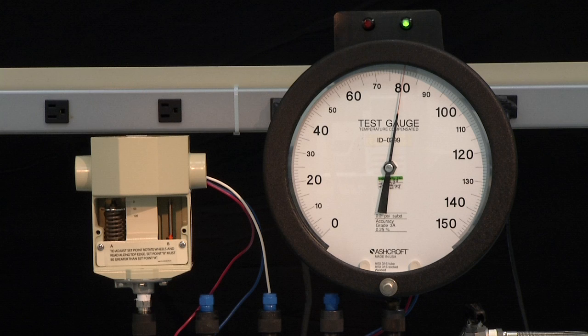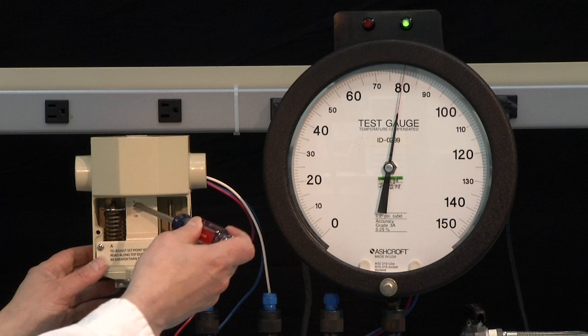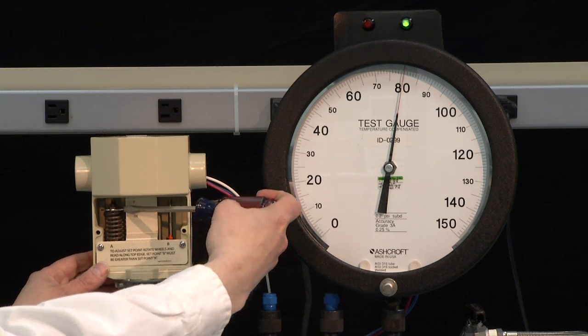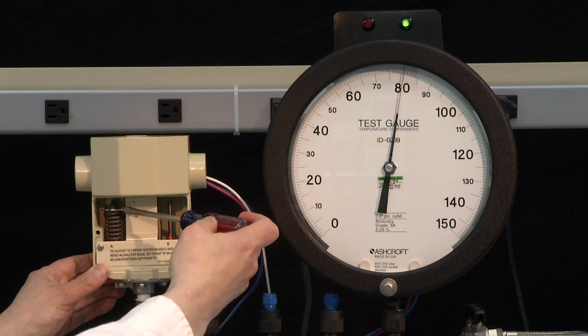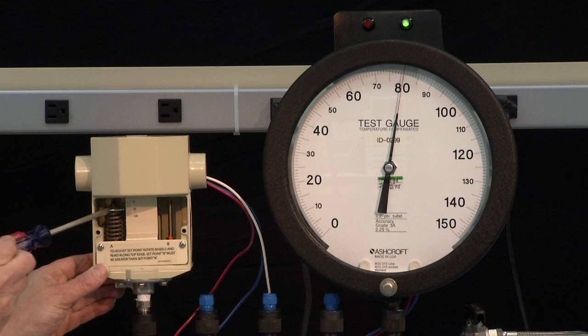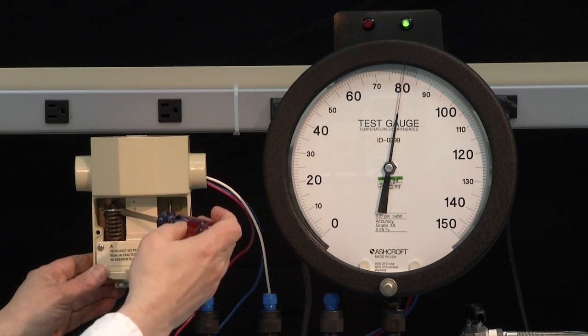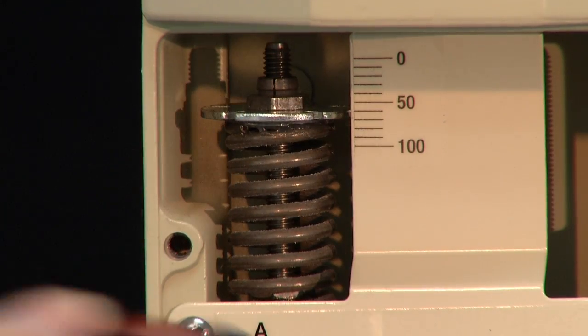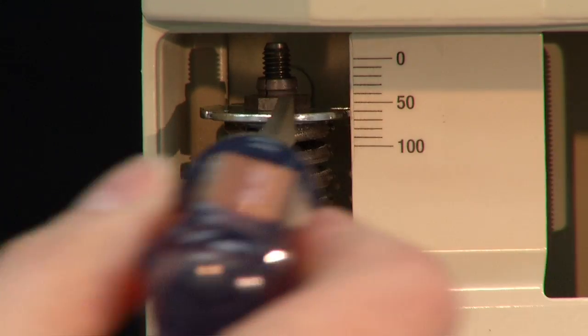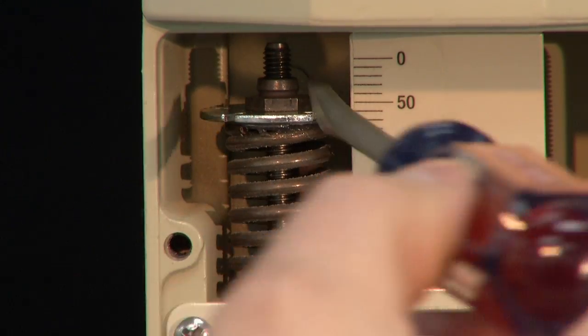Now, we are going to increase the set point of the switch, because it's already turned on, until it turns off, and then lower it back until it turns on again. We will set at 80 PSI increasing. We will start by putting a screwdriver into the slots onto the adjustment disk and turning it in a clockwise direction to increase the set point of the switch. We are going to do this all the way until the switch resets.